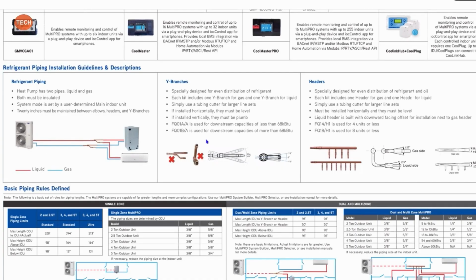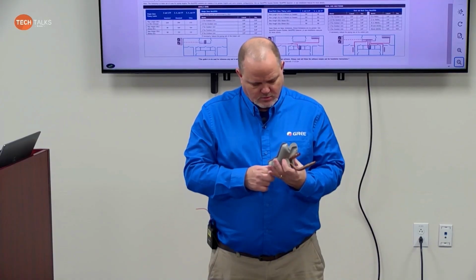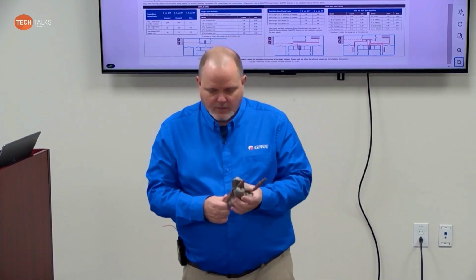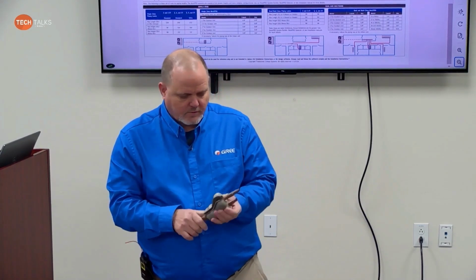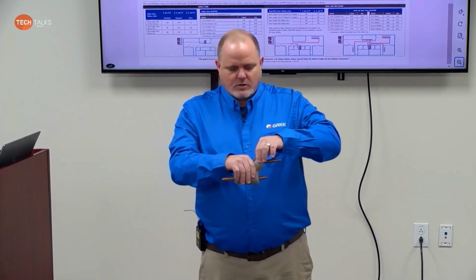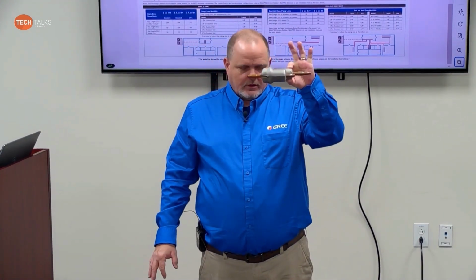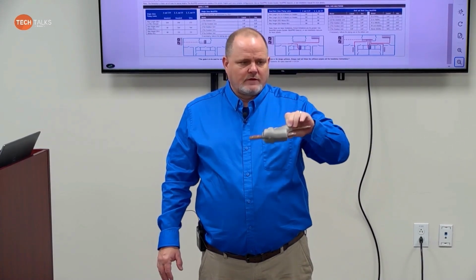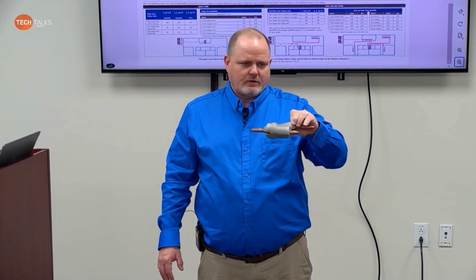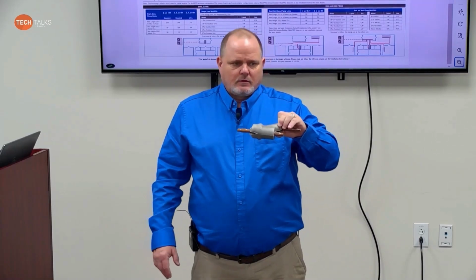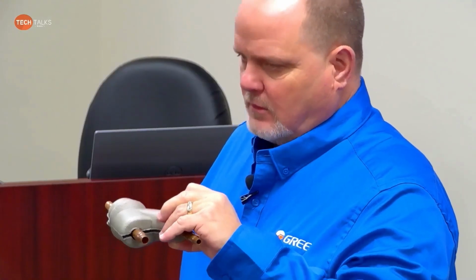Now each one of the Y branches you order, when you order it, you will get the liquid one and you will get the suction. And it also comes with the insulation jacket that goes around it. But each header assembly you order gives you one for liquid, one for gas. You don't have to order them separate. You don't have to order two of the part number. Correct. It comes with both. Each box will have one liquid, one gas.